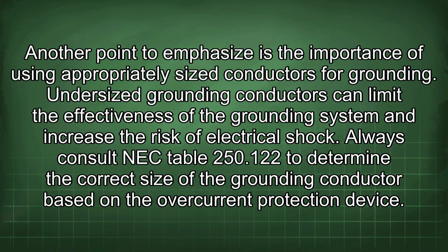Another point to emphasize is the importance of using appropriately sized conductors for grounding. Undersized grounding conductors can limit the effectiveness of the grounding system and increase the risk of electrical shock. Always consult NEC Table 250.122 to determine the correct size of the grounding conductor based on the overcurrent protection device.